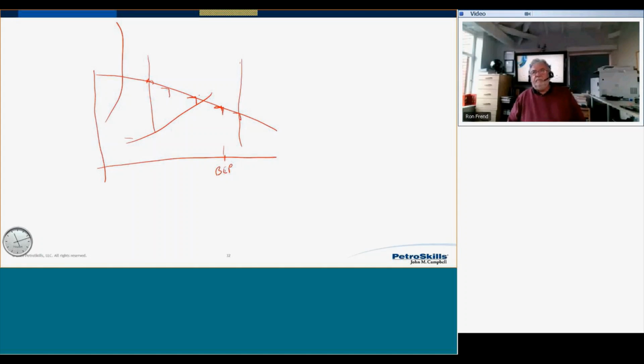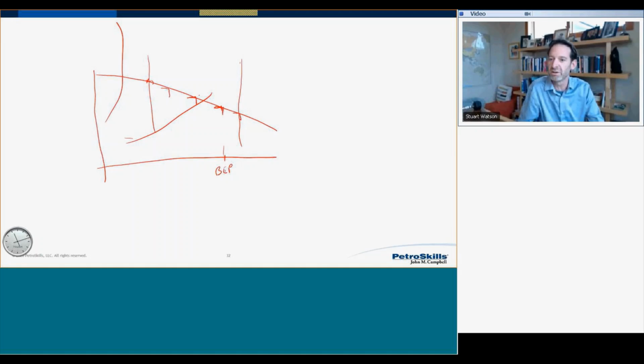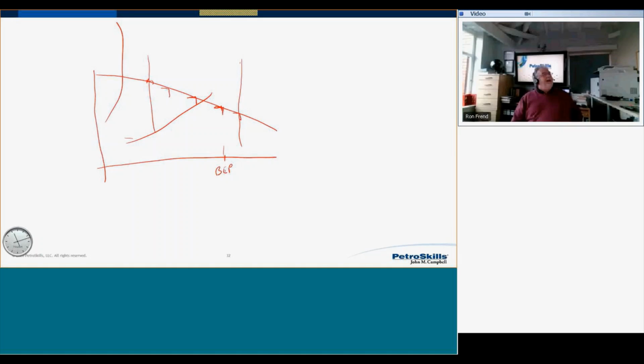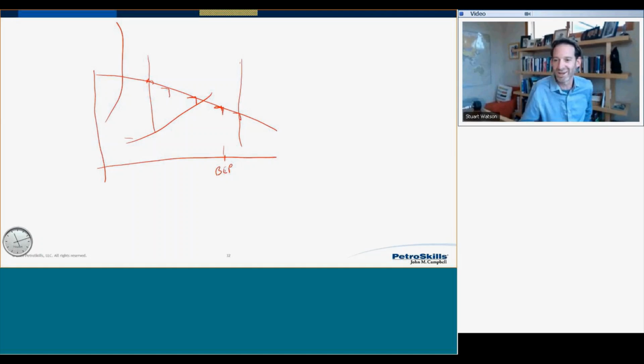So here's another fantastic question. How do we adjust the original vendor pump curve to account for age? My short answer to that, because I've had a few minutes to think about it, and I'll let you percolate, Ron, is testing. Depending on the application of the pump, depending on what the pump is doing, you could have a lot of erosion and corrosion to the impeller. And the moment you start to deteriorate the shape of the blades, the diameter, the tip shape, you're going to deteriorate the performance of the pump.